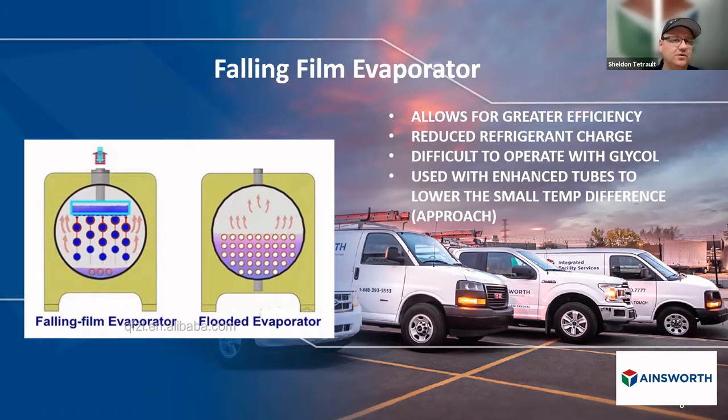So as you guys are doing refrigerant management, if you just look at the nameplates, some of the machines are going from 2,500 pounds of refrigerant down to 1,200, which really is a cost savings on the machine itself, because if any of you have dealt with a leak, refrigerant is not cheap.